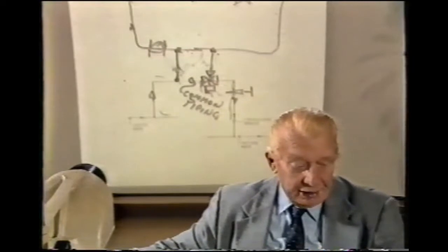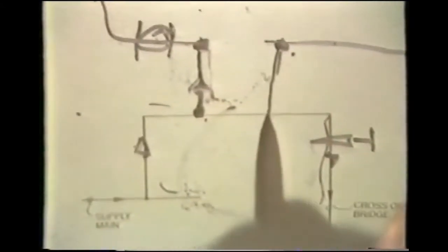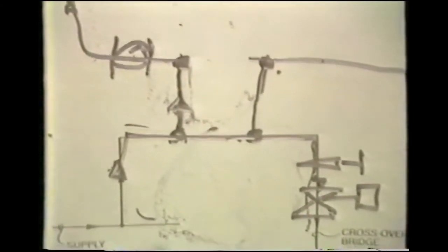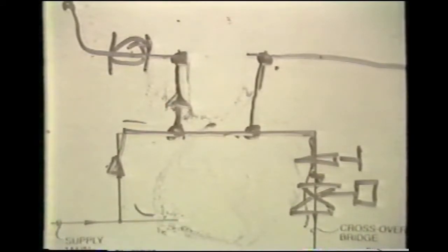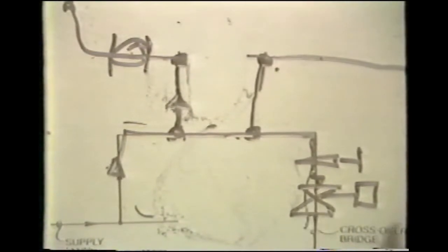Now, a third development that occurred later has to do with a diversified flow in the distribution system and/or a variable flow rate through that distribution system. And what we would do in this circumstance then is to change the distribution in such a way that we maintain the common piping in the crossover bridge, but we provide control by means of a two-way control valve in the crossover bridge supply or return. It makes no difference in terms of flow rate as to whether that control valve, this two-way control valve, is applied in the return side of the crossover bridge or the supply side. It only establishes a difference in terms of the static pressure that we will have developed in the secondary circuit.